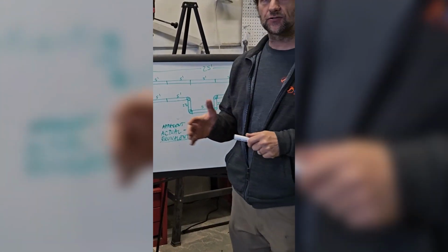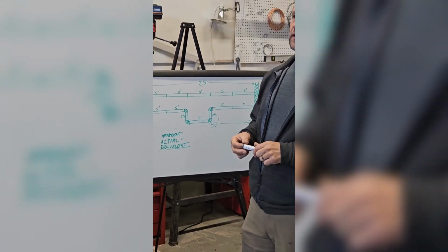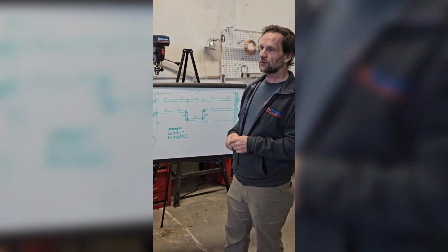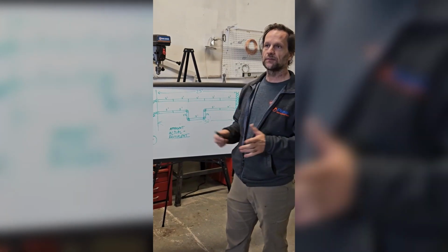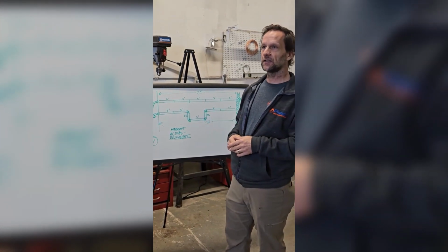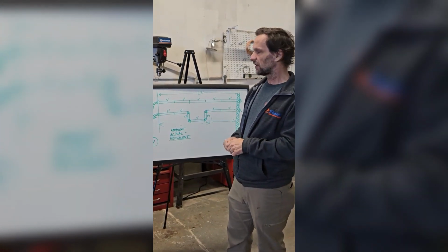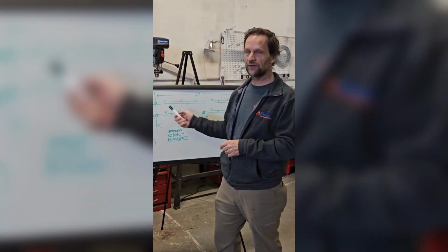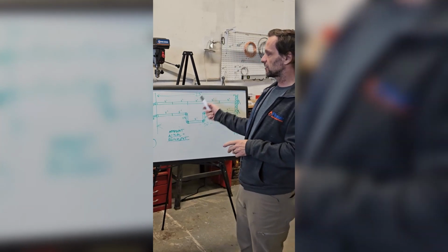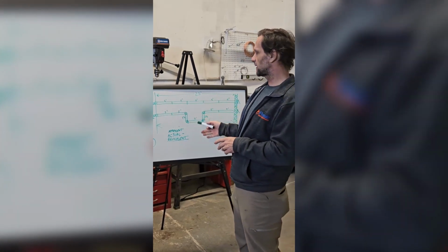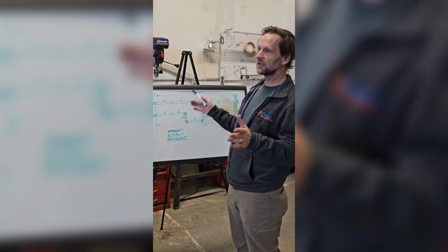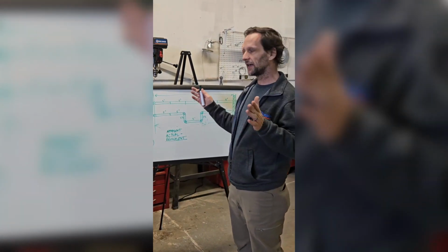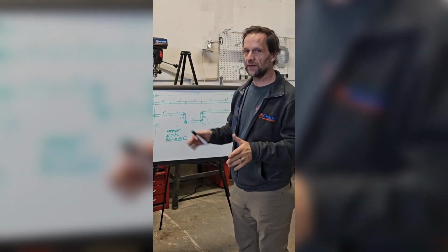The average dryer is capable of pushing the air through an exhaust system that's about 25 to 30 feet long without any restrictions, without any penalties on its performance. And again, this is a duct that has no obstructions. It's a clean duct, 30 feet long. Again, 30 feet of equivalent length.